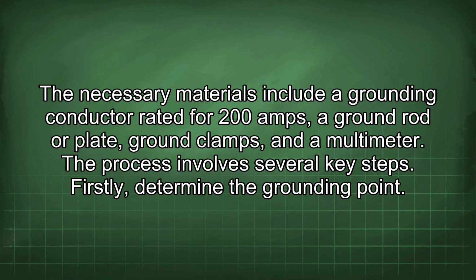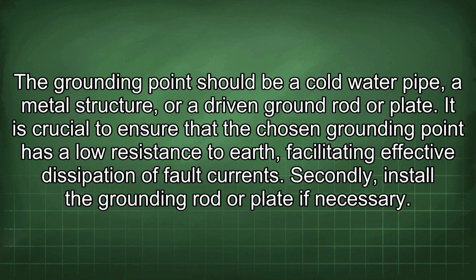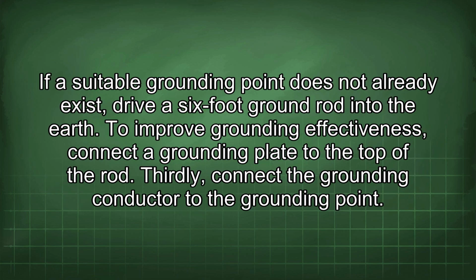Firstly, determine the grounding point. The grounding point should be a cold water pipe, a metal structure, or a driven ground rod or plate. It is crucial to ensure that the chosen grounding point has a low resistance to earth, facilitating effective dissipation of fault currents. Secondly, install the grounding rod or plate if necessary. If a suitable grounding point does not already exist, drive a 6-foot ground rod into the earth. To improve grounding effectiveness, connect a grounding plate to the top of the rod.